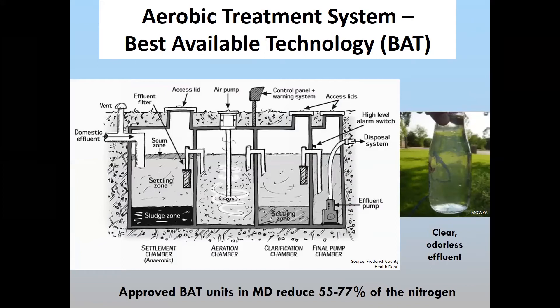BAT units provide advanced treatment — they supply aeration and oxygen to the bacteria, which helps break down organics. One of the advantages, beyond better nutrient and organic treatment, is that the effluent tends to be very clear compared to typical septic tank effluent. That actually allows for, in many cases depending upon the soil, a smaller drain field area and potentially prolongs the life of the drain field because you're not putting as much organic material out there.